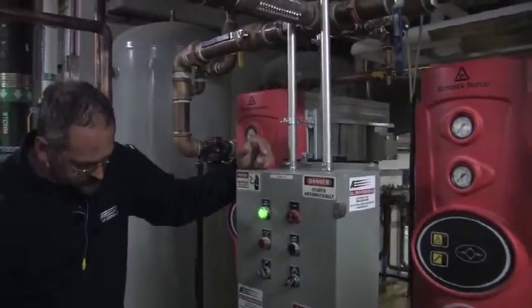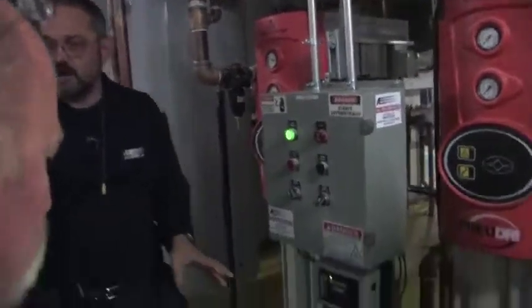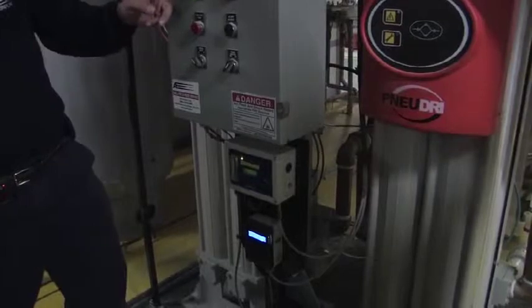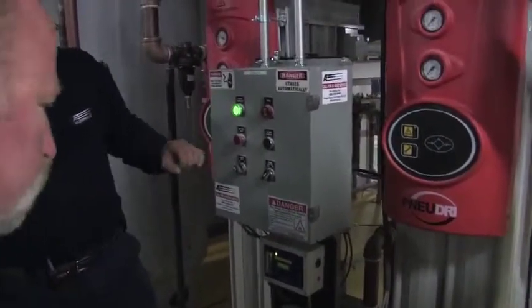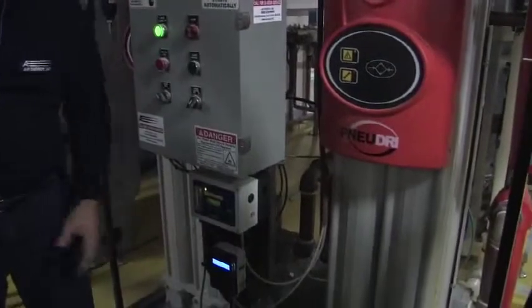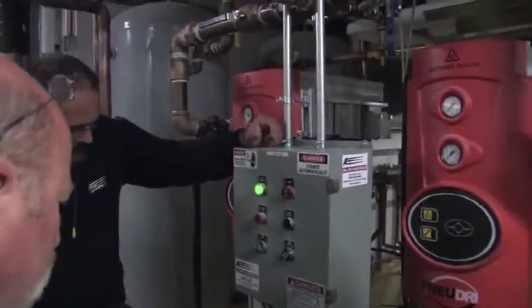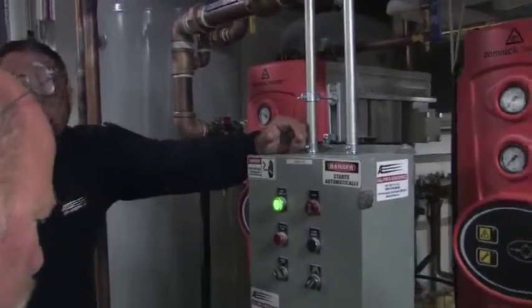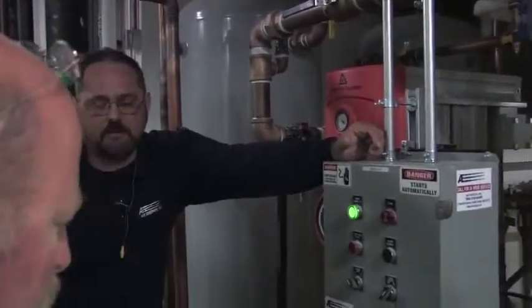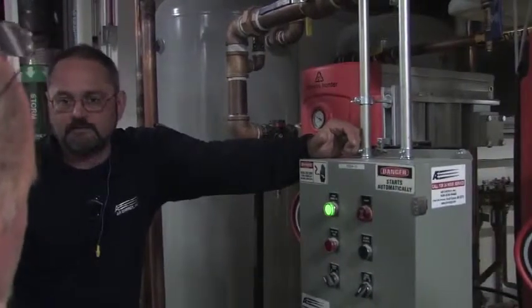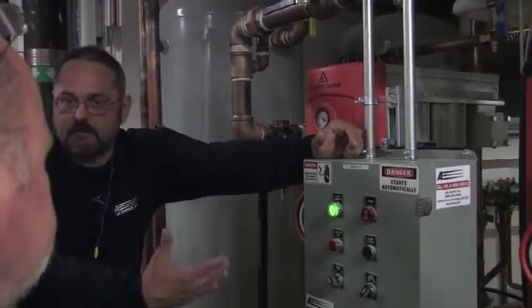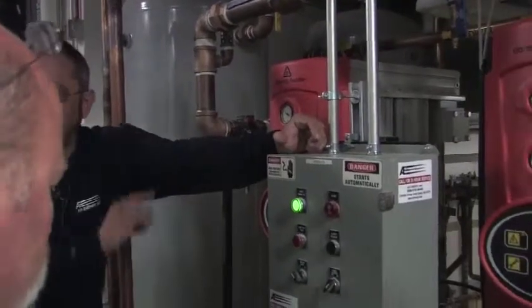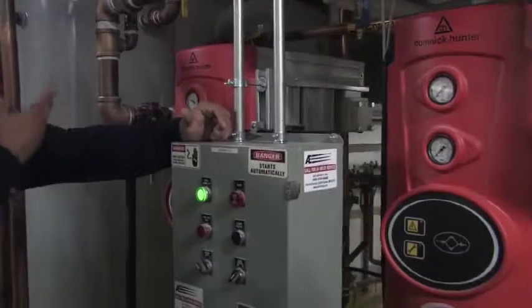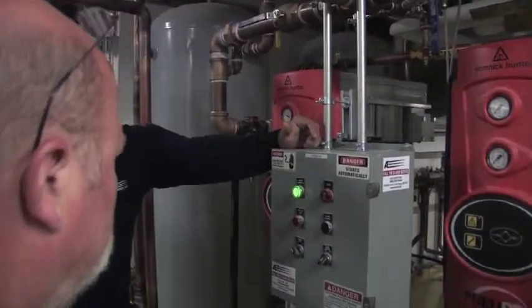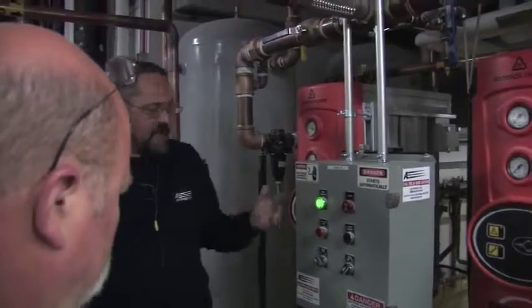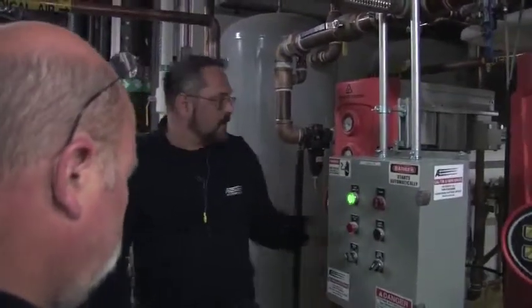That's running dryer. Yep. Now this one, the other thing this does is runs the dryer. You'll see that we have a thing here that says Purge Saver on. Okay, there's a second program set point on this, and that set point is set to minus, I believe on this one it's either minus 10 to plus 10 or minus 20 to 0, because we only need to be under 32 to 35. So I would try to give you about 20 degrees of cushion, so to speak, but there's no need to have this dryer shoot all the way down to minus 80, which is where it can go at full purge rate.